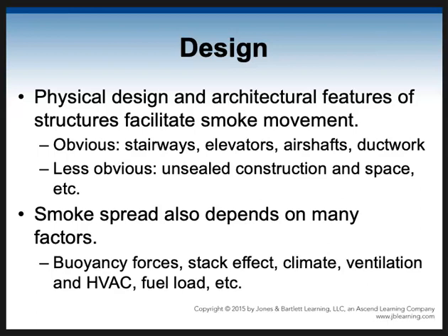So smoke spread depends on a lot of different factors. And this is why, especially in these large buildings we're talking about, we need an engineer. Because there's buoyancy forces, there's stack effect. Stack effect is where the hot air rises to a point that it starts to cool off, and it hits cold air, and now it just stops, and you have this big stack of smoke, and it won't go any higher until the heat builds up to take it to a higher level.